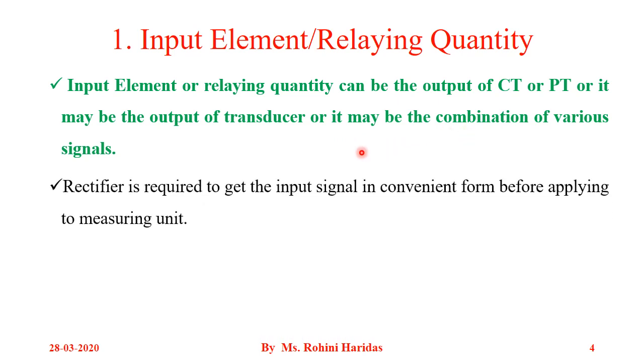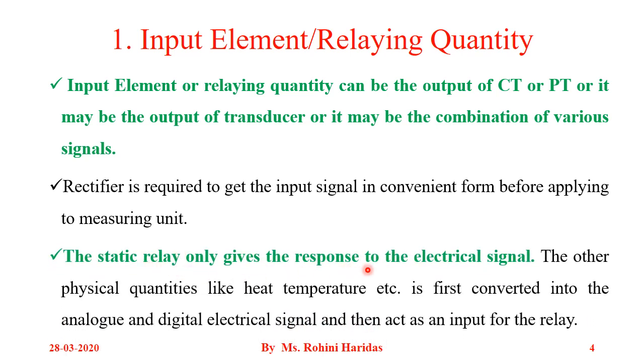The first one is the input element and the relaying quantity. The input element or relaying quantity can be the output of the CT or PT, or it may be the output of a transducer, or it may be a combination of various signals. A rectifier is required to get the input signal in a convenient form before applying it to the measuring unit. A static relay only gives response to electrical signals; other physical quantities like heat and temperature are first converted into analog and digital electrical signals and then act as input.